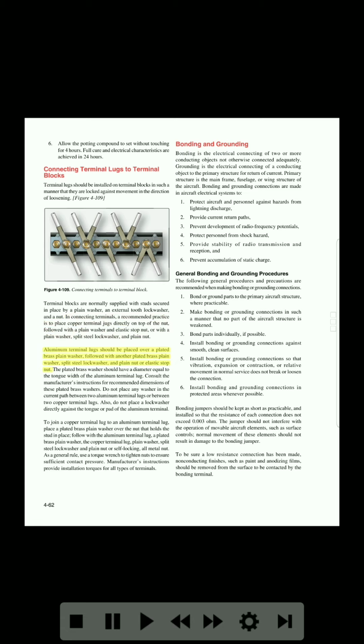nut. Aluminum terminal lugs should be placed over a plated brass plain washer, followed with another plated brass plain washer, split steel lock washer, and plain nut or elastic stop nut. The plated brass washer should have a diameter equal to the tongue width of the aluminum terminal lug. Consult the manufacturer's instructions for recommended dimensions of these plated brass washers. Do not place any washer in the current path between 2 aluminum terminal lugs, or between 2 copper terminal lugs. Also, do not place a lock washer directly against the tongue or pad of the aluminum terminal.